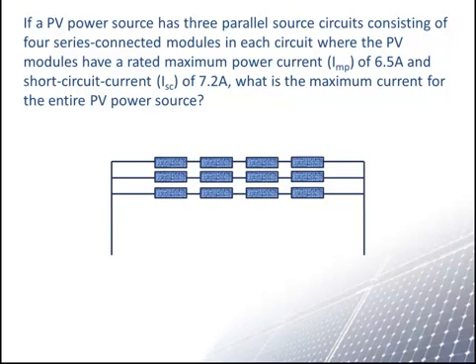A PV power source has three parallel source circuits, also called strings. Each string consists of four series connected modules where each PV module has a rated maximum power current, I-sub-MP, of 6.5 amps and a short circuit current, I-sub-SC, of 7.2 amps. What is the maximum current for the entire PV power source?